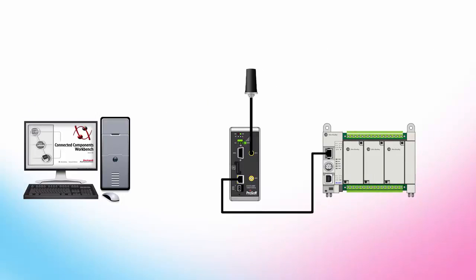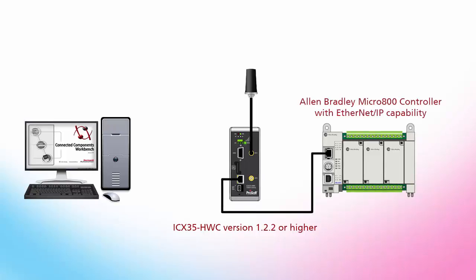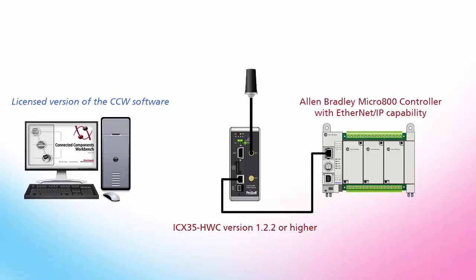Before we begin, I'll list the requirements for the configuration. You will need an ICX35 wireless gateway with firmware version 1.2.2 or higher, an Allen Bradley Micro 800 controller with Ethernet IP capability which would be either the Micro 820 or the Micro 850, a licensed version of the CCW software installed on your machine, and finally the ICX35 SMS sample CCW project version 1.7.